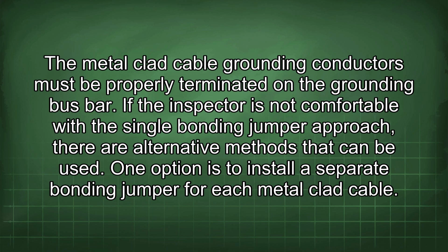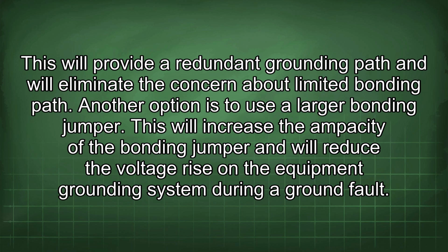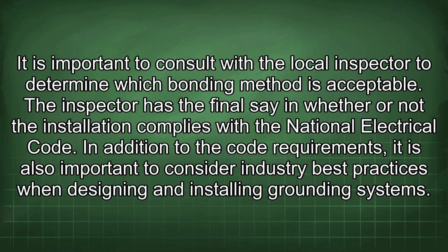One option is to install a separate bonding jumper for each metal-clad cable. This will provide a redundant grounding path and will eliminate the concern about limited bonding path. Another option is to use a larger bonding jumper. This will increase the ampacity of the bonding jumper and will reduce the voltage rise on the equipment grounding system during a ground fault. It is important to consult with the local inspector to determine which bonding method is acceptable.